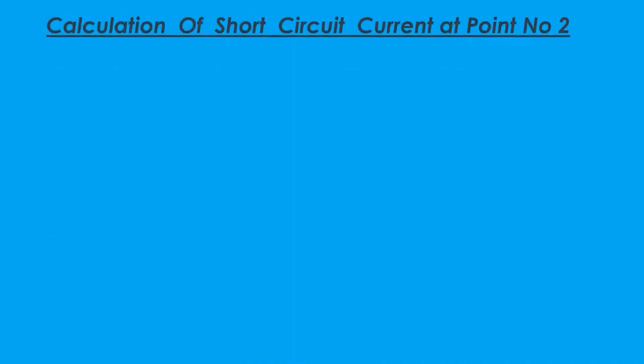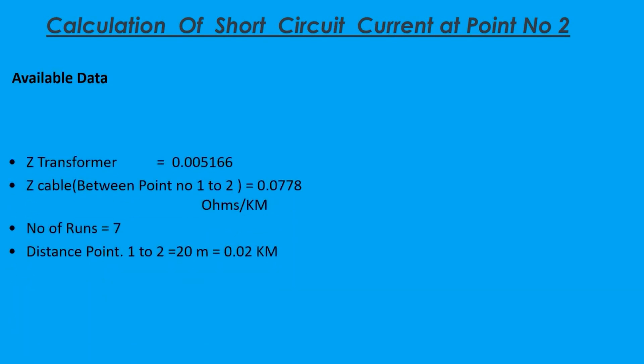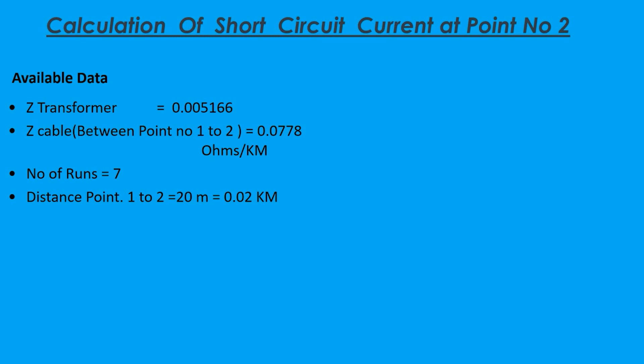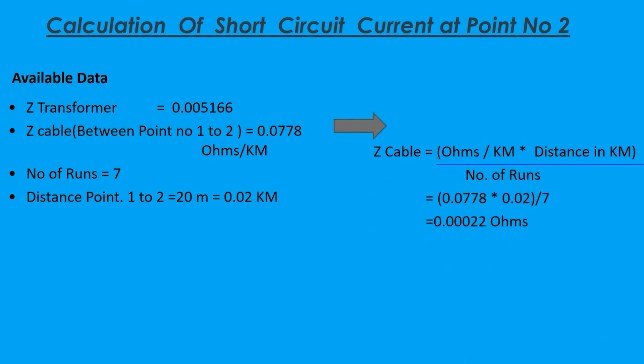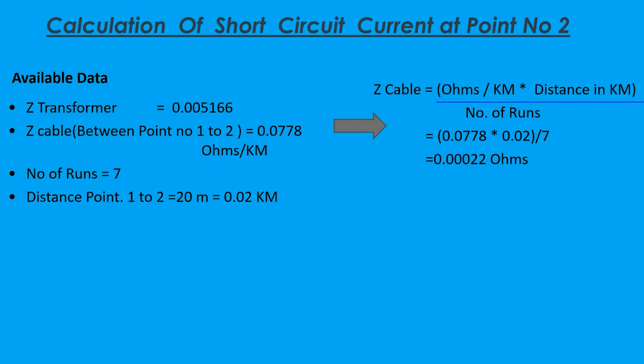For calculation of short circuit current at point number two, available data: Z transformer is 0.005166 ohms. Z cable between point number one and two is 0.0778 ohms per kilometre. Number of runs are seven and the distance from point one to two is 20 metres, which is 0.02 kilometres. Z cable equals ohms per kilometre multiplied by distance in kilometres divided by number of runs, giving 0.0778 times 0.02 divided by 7, which equals 0.00022 ohms.